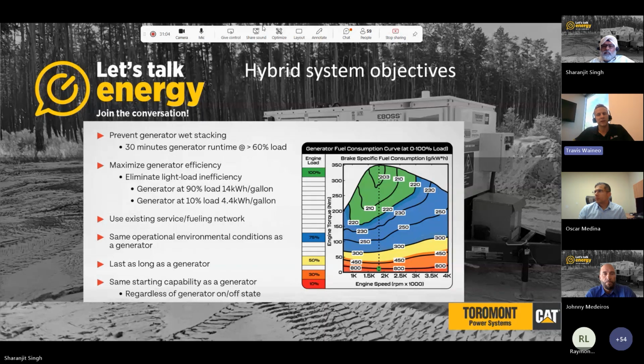At 90% load, that generator is much more efficient. You're getting about 4 times the efficiency at 14 kilowatt hours per gallon at 90% load. So now what we're trying to do is maintain that generator efficiency even on a light load on the output scenario to make sure we're getting the max amount of energy per gallon of diesel we put into that generator.